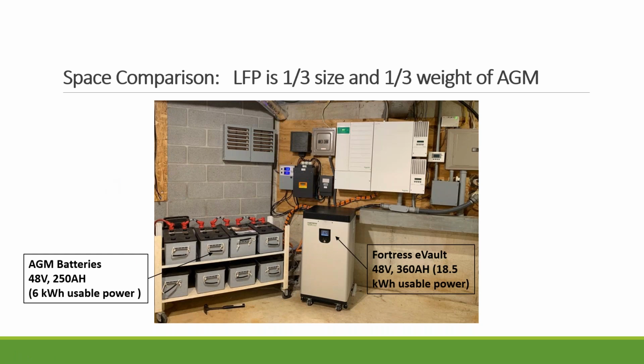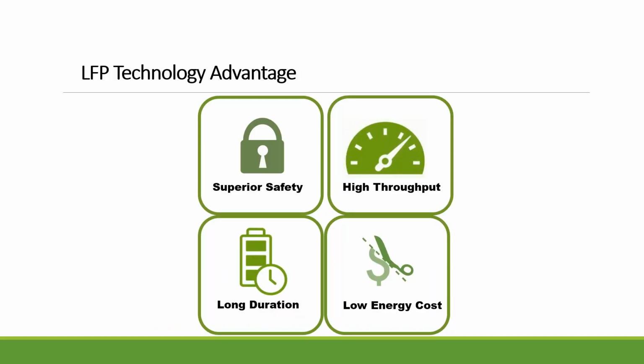Here is just an example showing the space requirements of the 2 different technologies. On the left is AGM. It's 48 volts, 250 amp hours, with 6 kilowatt hours of usable power. On the right is a Fortress eVault with 18.5 kilowatt hours of usable capacity. As you can see, it only needs about 1/3 of the space, but you actually have more usable capacity. So the overall advantage of LFP chemistry: we talk about safety, very high energy throughput, it lasts very long, and all of it leads to very low energy cost. And that's important information, the low energy cost.